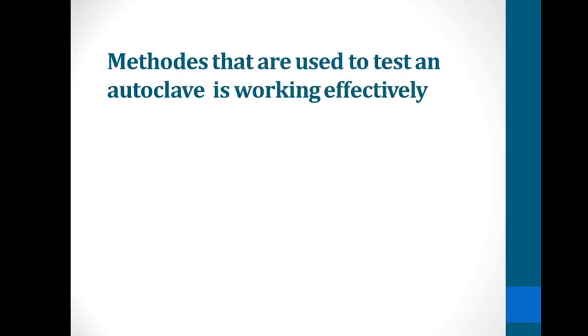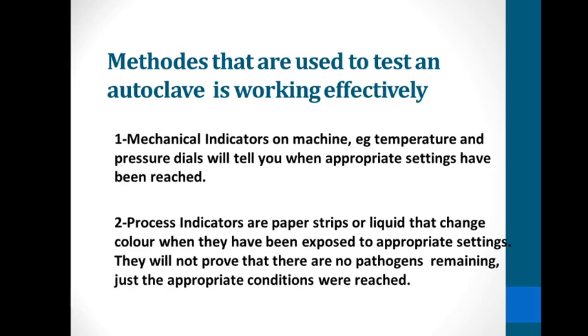There are methods used to test whether an autoclave is working effectively. The first is mechanical indicators: temperature and pressure dials on the machine tell you when appropriate settings have been reached. The second is process indicators: paper strips or liquid that change color when exposed to appropriate settings, though they do not prove that no pathogens remain — only that the appropriate conditions were reached.